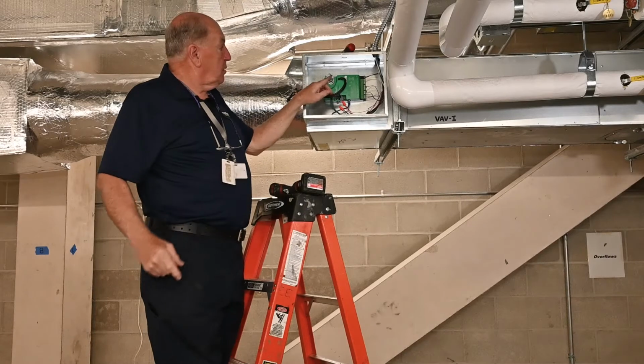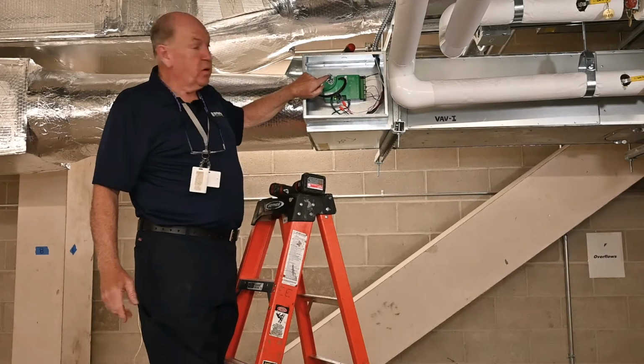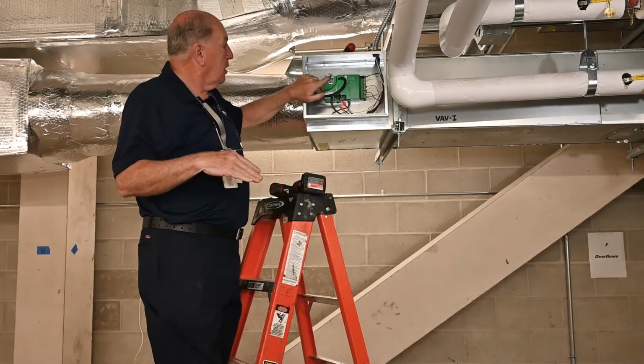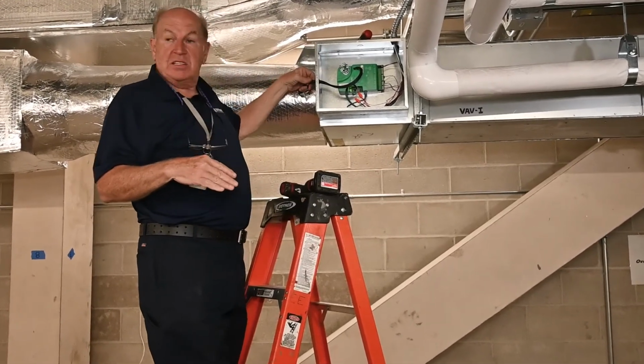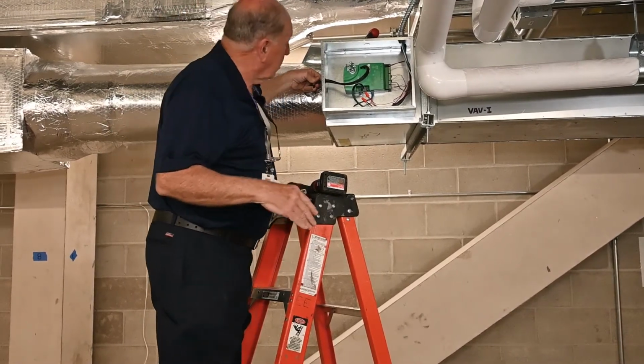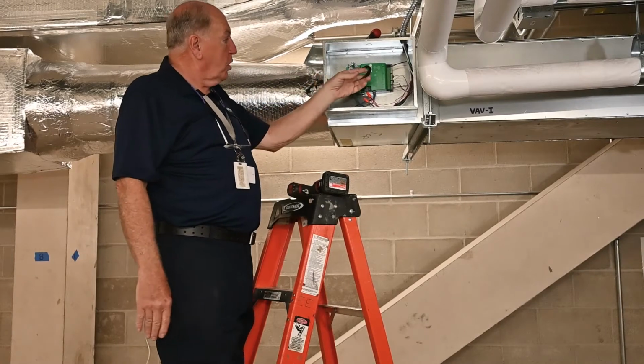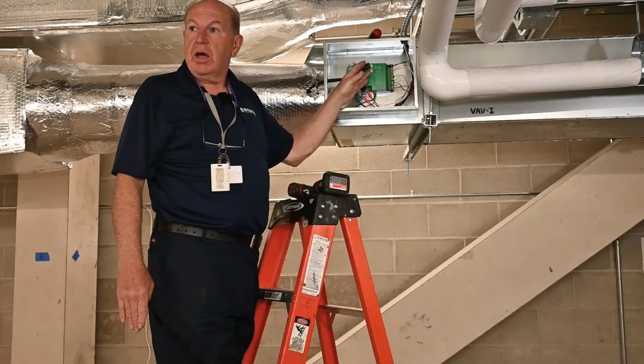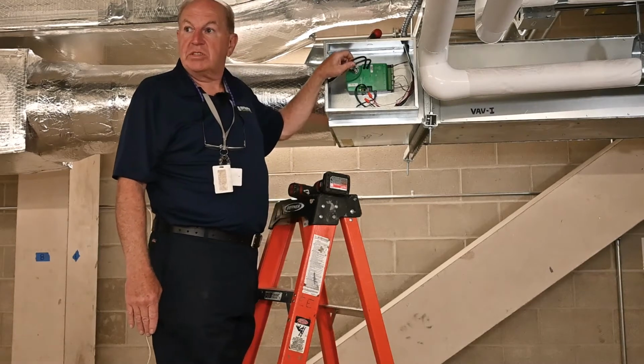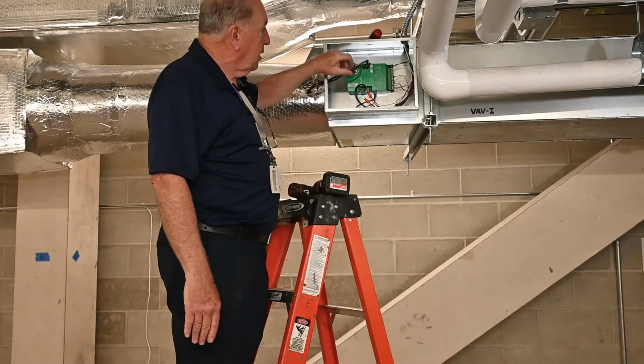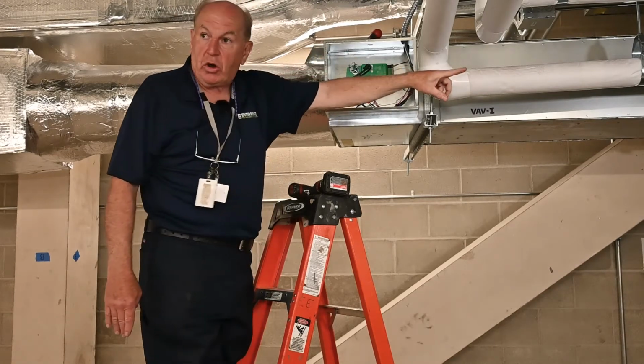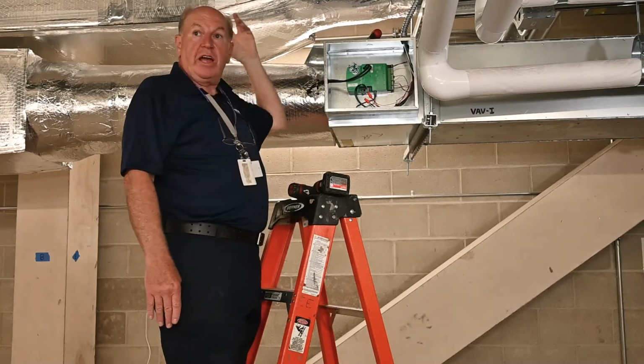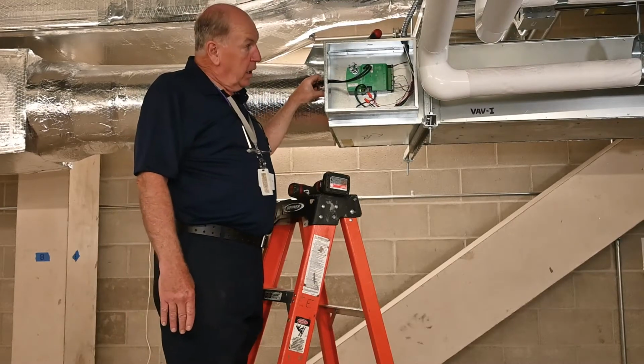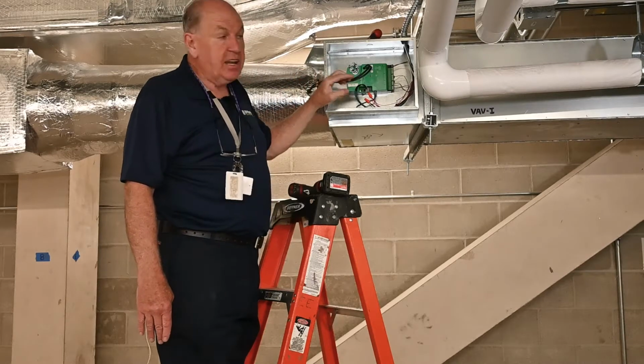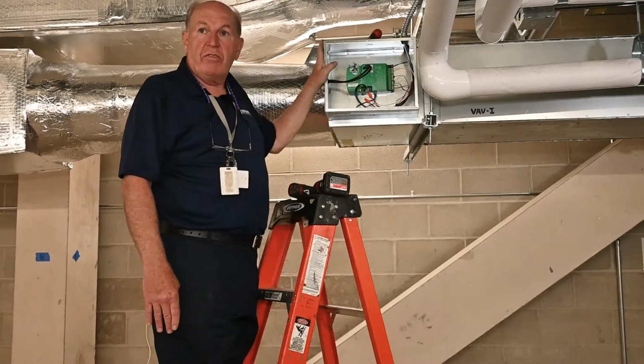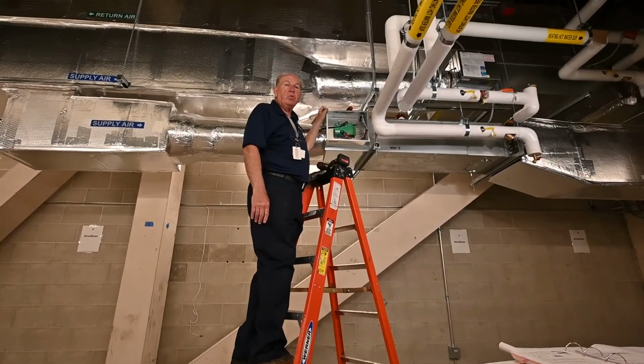It's simply that shaft marking, when it's horizontal with the ductwork, it's wide open. It's throttling down right now. There's an airflow sensing tubes here that go right to this controller. The VAV controller has a space sensor and will control airflow to match the demand. Also, this is linked to a reheat coil because we're bringing in the cold air from the rooftop unit and air handler, and as needed, the reheat coil valve will open and close. They'll go over more of that on the ATC training, which is in a few weeks.